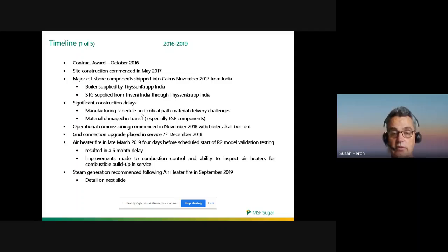Just when we'd finished our steam blows and thought we had everything ready to go, we were 4 days short of wanting to commence our first scheduled R2 testing. Back in April 2019, we had a very bad air heater fire on the shutdown immediately prior to that, where a lot of combustibles had built up within the air heater, ignited, and got hot enough to reach a metal fire condition.